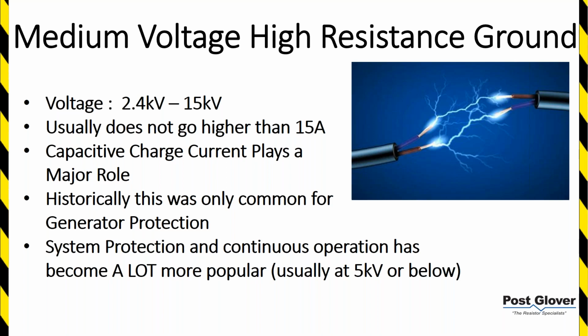I would say more recently, and people can argue how long ago it's been, from my perspective you saw some 10, 15 years ago, but it's getting a lot more popular now. And honestly, I think there's a little bit of controversy about where high resistance ground is safe. I don't think that controversy exists at 5 kV or below, so that's kind of where I recommend it. What I always tell engineers, I have talked to engineers who have used medium voltage high resistance ground continuously at higher voltages. But if you're not a person who's comfortable with that and understands it, I would say just go with the consensus at 5 kV or below.